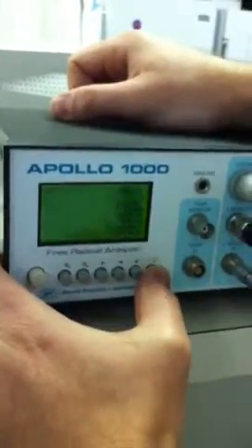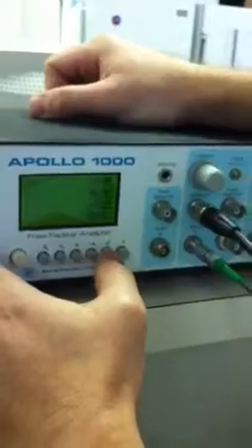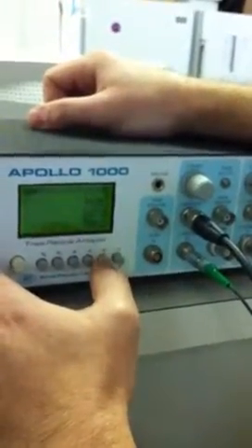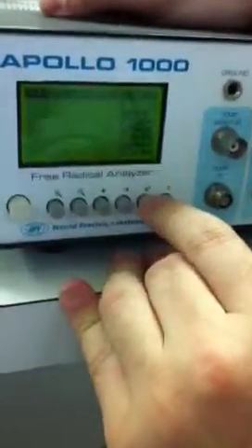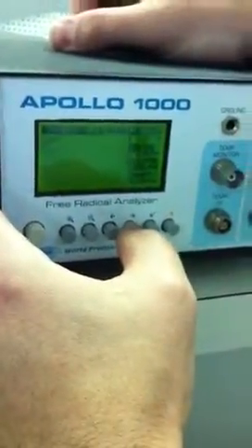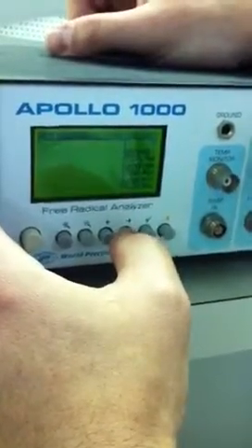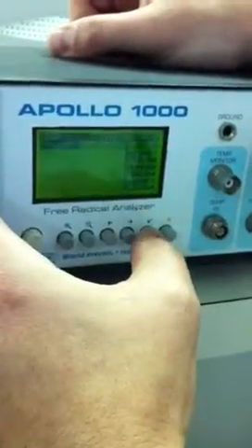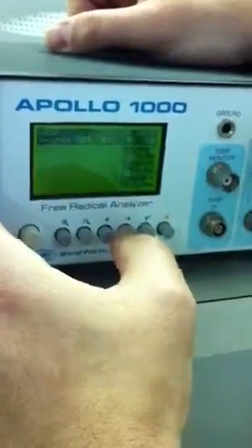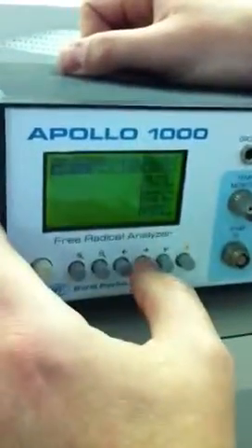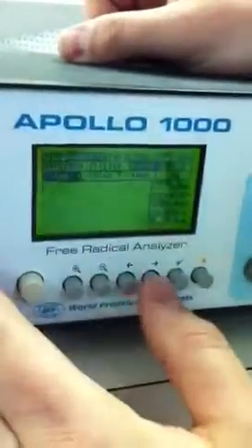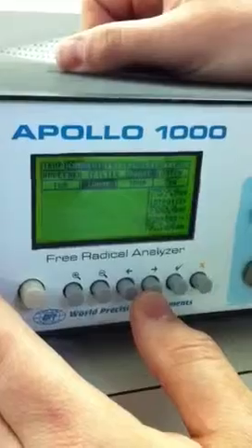100 nanoamps. Right, and I'm going to go to the menu, which you can access by first hitting the X button, then hitting the checkmark button. Now you have different options which you can scroll for temperature. I'm going to check current, highlight that, and then there's a sub-menu, waveform. I'm going to go over to range and check that. And here, now it's 1 microamp highlighted.